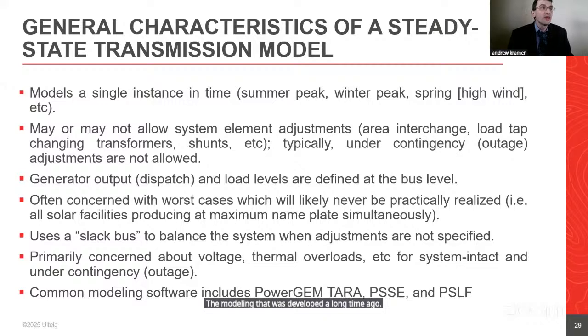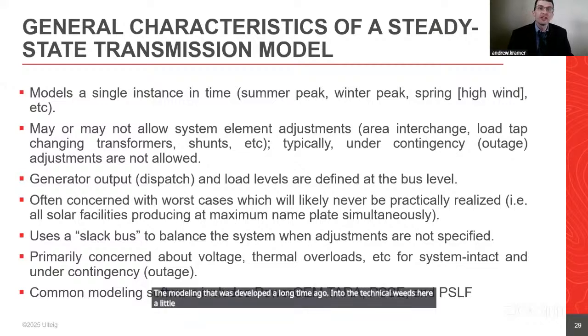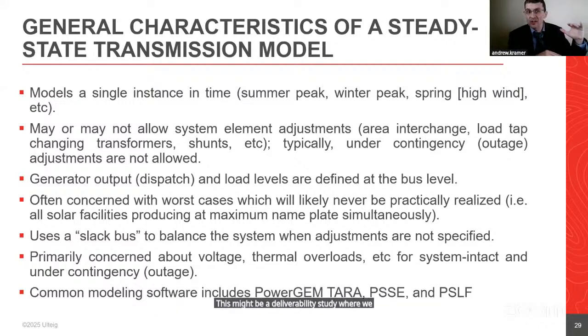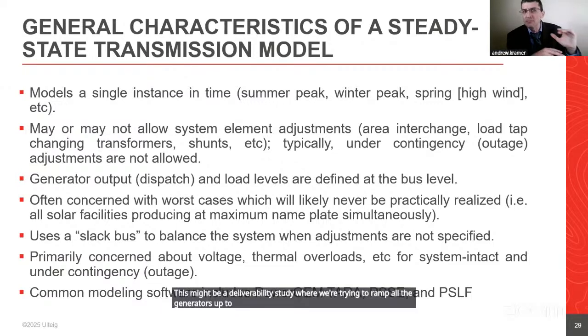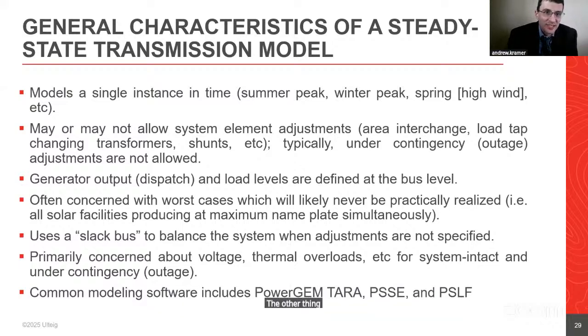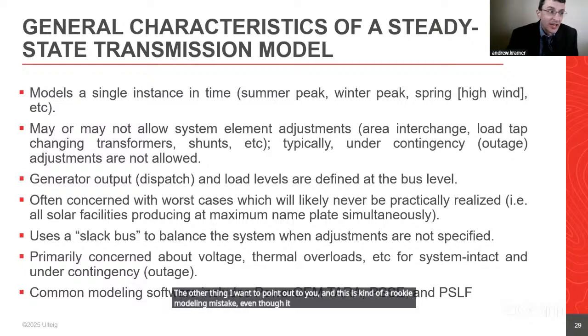Into the technical weeds here a little bit: a lot of times we're interested in what we call the worst case. This might be a deliverability study where we're trying to ramp all the generators up to maximum and see if we can really get these megawatts out of this generator. It doesn't really tell you if it's curtailed or not, but it tells you if you may or may not have an issue. We'll get into curtailment, outage, and curtailment duration in a bit. Still useful information though. The other thing I want to point out is kind of a rookie modeling mistake, though a bit technical, I think people can appreciate it.